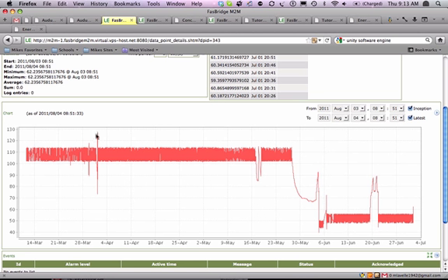Notice that we've had some interruptions here. We had a power failure in which the compressors took off and did their thing, if you will, and it didn't seem to be a big problem here. We also had a power failure here, and the temperature actually went up, and they were hit by lightning at the far end of the chart. Nevertheless, it's a great way of taking a look at what's going on.